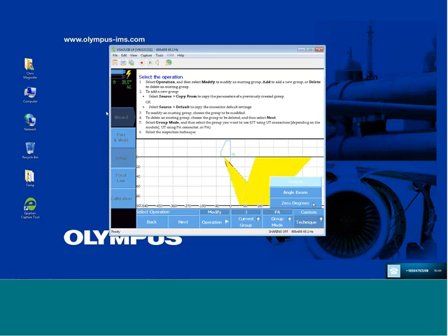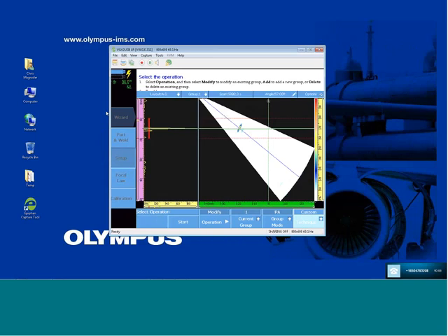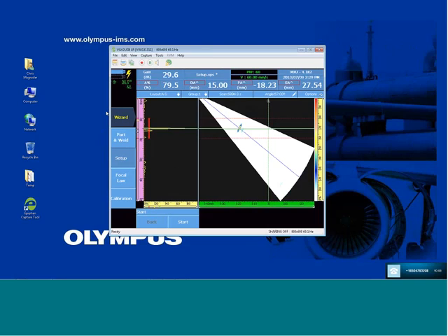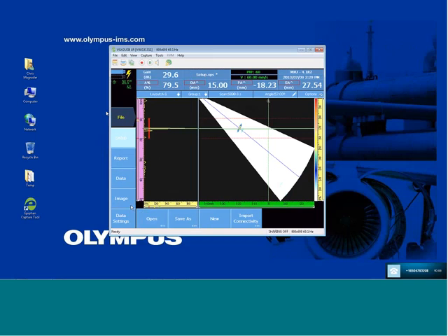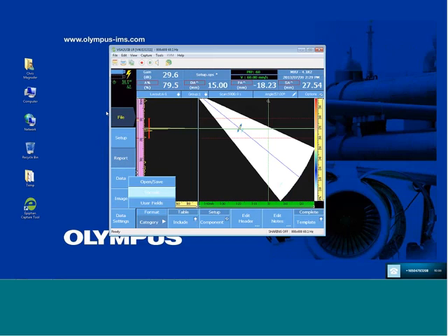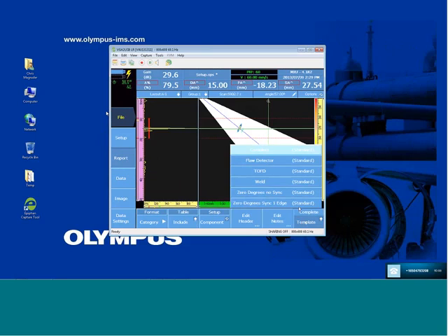So another feature, and probably the most important one I would hope you would take away from this webinar, is something simple that we did to help customers improve their measurements and calibrations. Generally, when calibrating wedge delay, people perform the wizard function automatically regardless of the condition of the current signal.